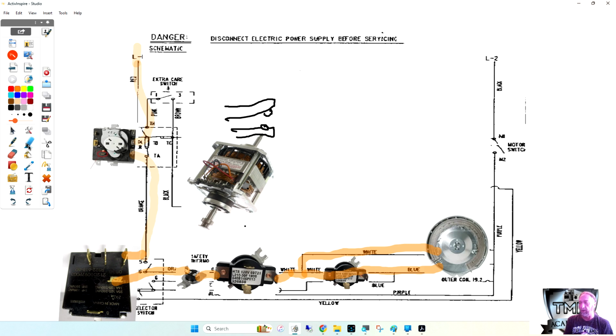Now the wire's running hot from inside, melting the plastic, which eventually burns. The only other thing that would cause that is if the element terminal itself, where the wire connects, is rusted or corroded. That would also cause a higher current draw and cause a premature failure.